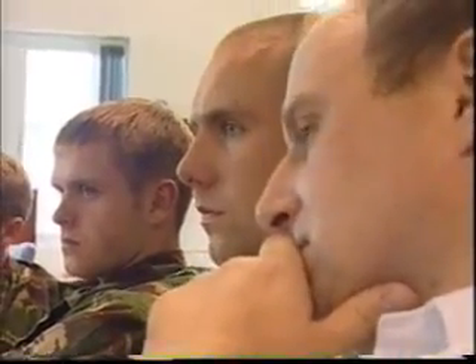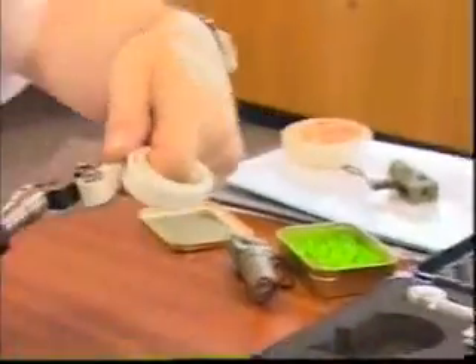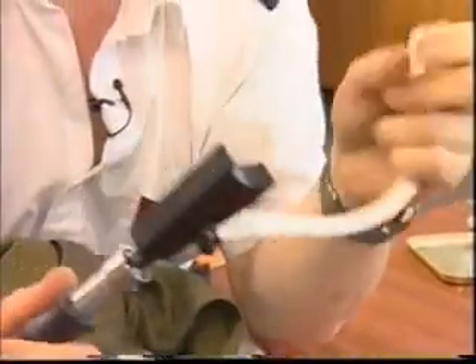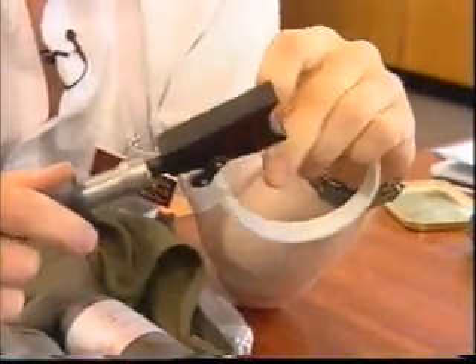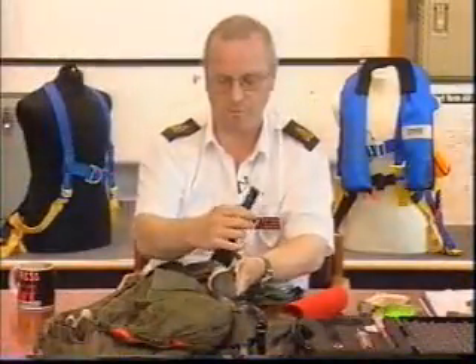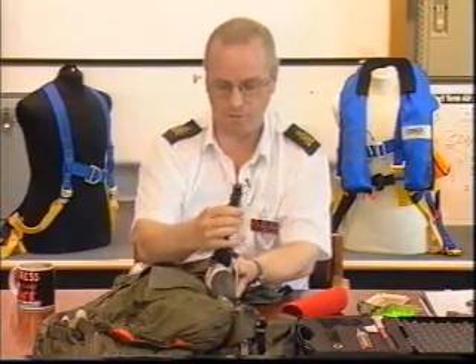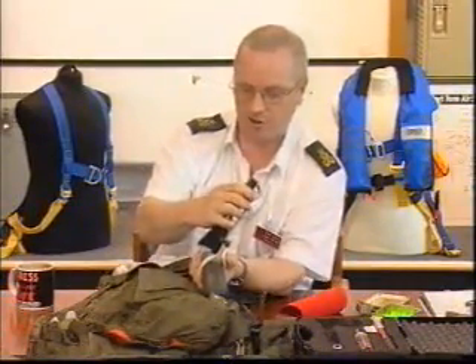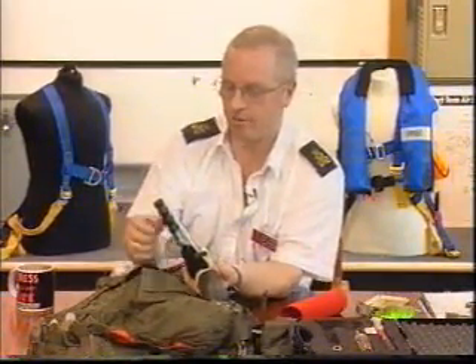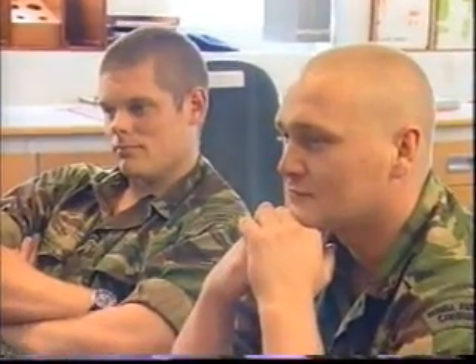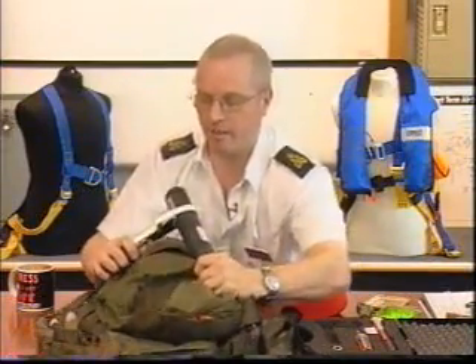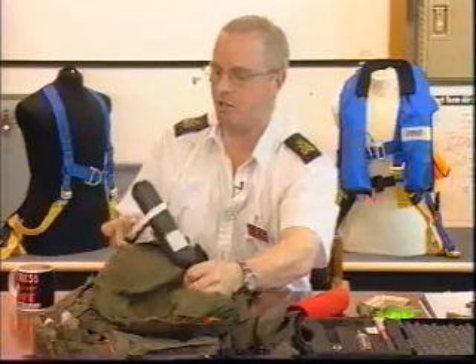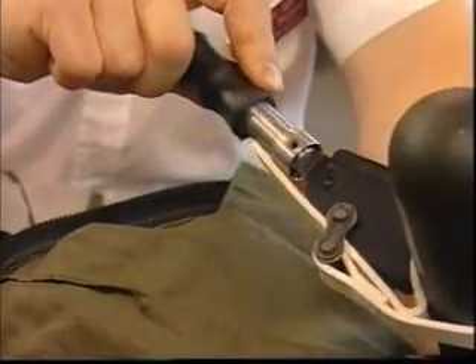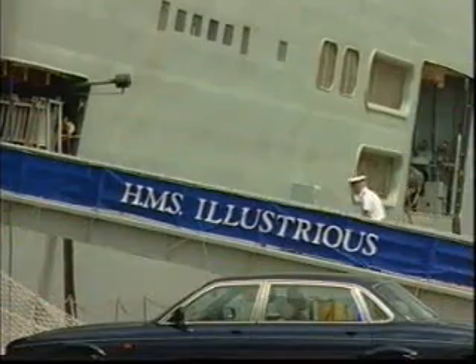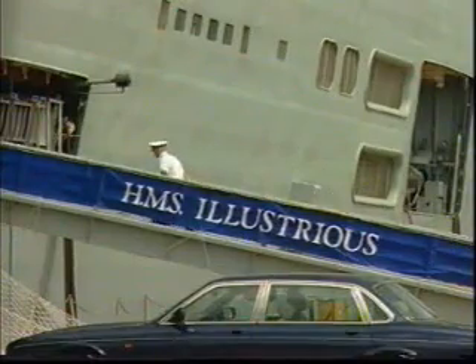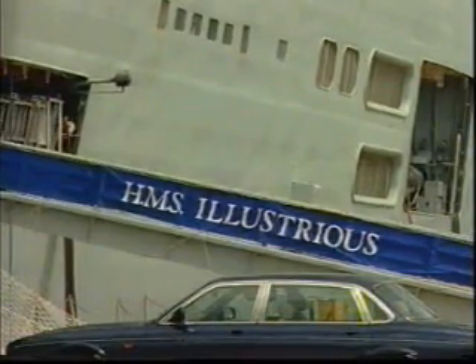And what we need to use is this strap wrench. Now this is preset at 35 pound-inches, alright? And it's very, very simple to use. All we do is bring it over, and what we're trying to achieve at this point is a square face between the torque wrench and the cylinder, alright? Once it's on, just support the strap, support the head, and all we do is we turn. And eventually it just breaks. Alright? That's it. Here we see the toolkit in operational use on the aircraft carrier HMS Illustrious.